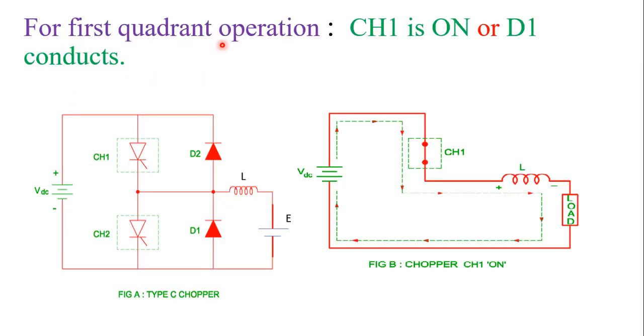For first quadrant operation, CH1 is turned on or diode D1 conducts. When chopper CH1 is turned on, the current path is: VDC, CH1, inductor charging with polarity positive and negative, load, and back to VDC. The current is positive in this case and the voltage is also positive, so the device works in the first quadrant.